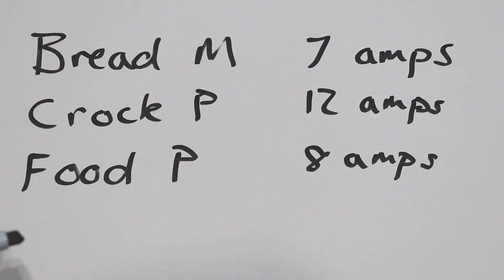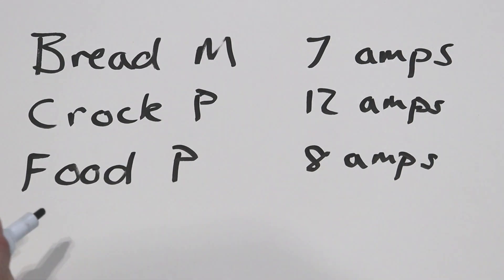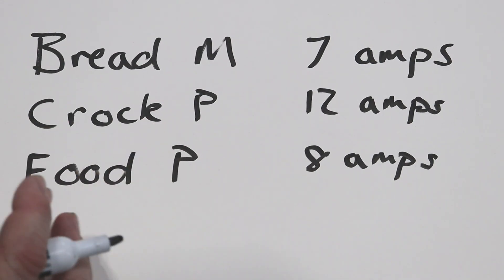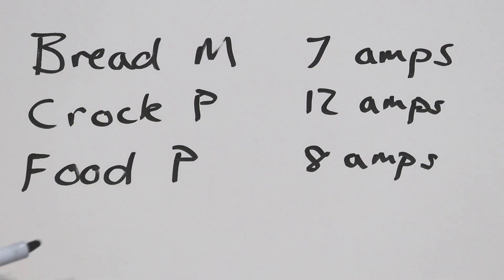So let's just base it off from these three appliances. Let's say worst case scenario, she's going to be using these three appliances at one time. So how many outlets would you put in? If you combine the bread maker and the food processor, you're at 15 amps and on a 20 amp circuit you'd be fine. The crock pot would have to be by itself because it's at 12 amps.